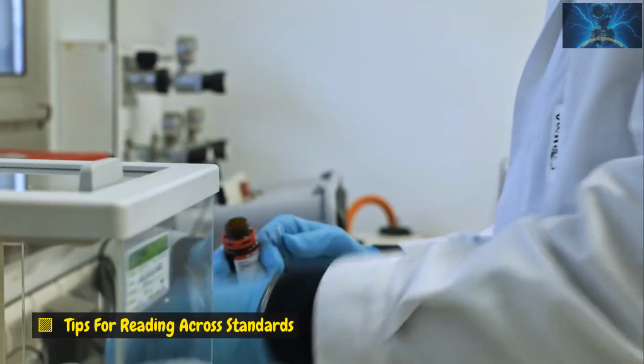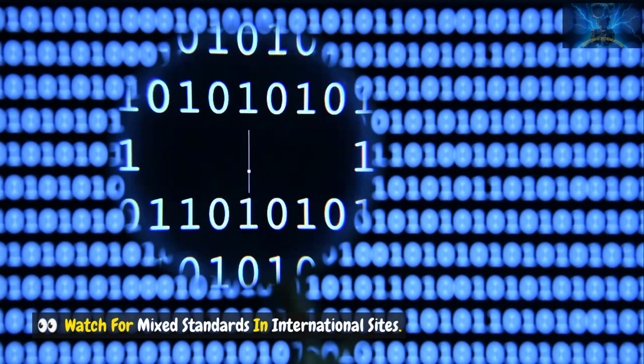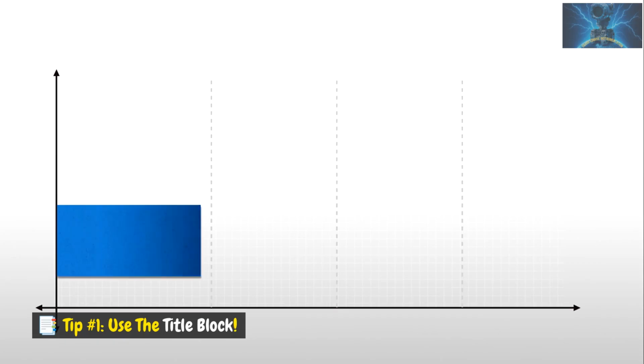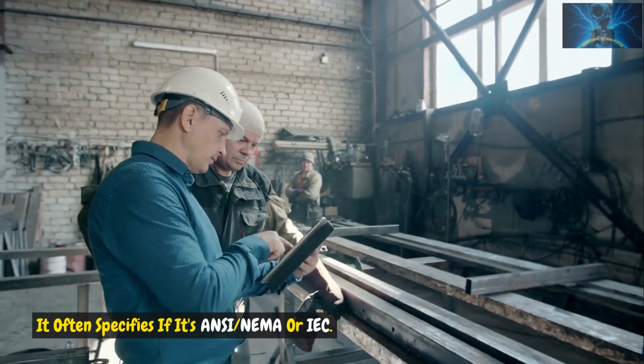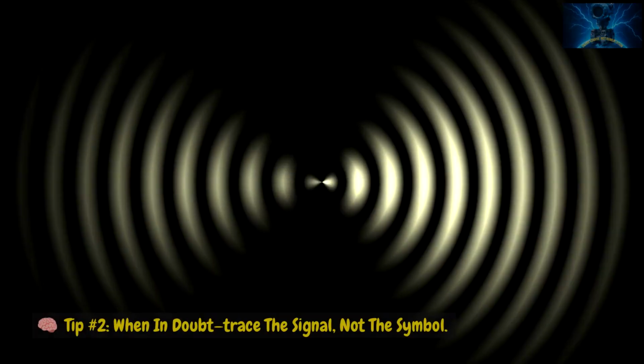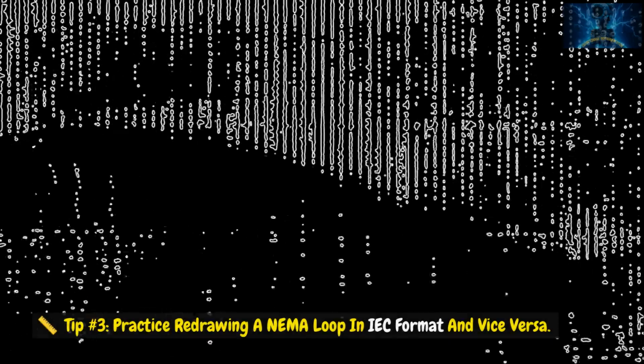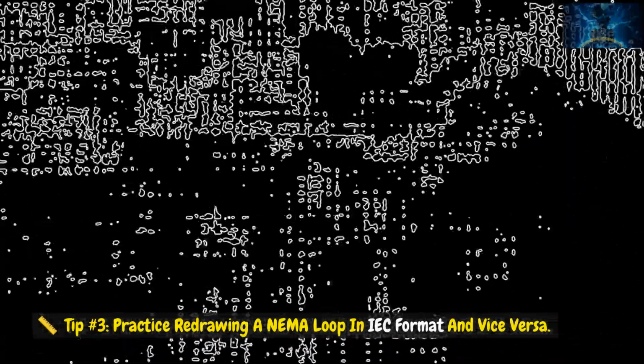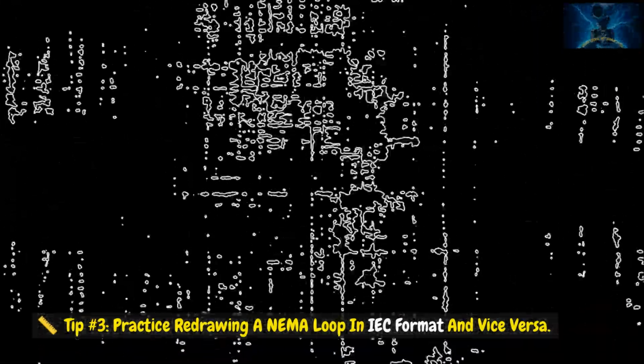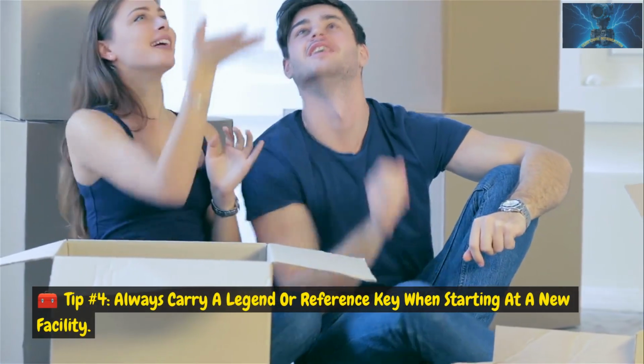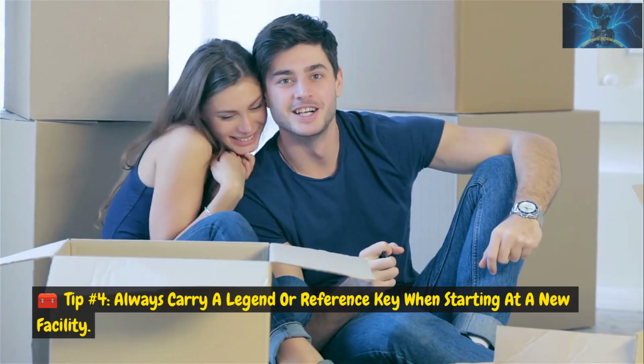Tips for reading across standards. Watch for mixed standards in international sites. Tip number 1: use the title block. It often specifies if it's ANSI, NEMA, or IEC. Tip number 2: when in doubt, trace the signal, not the symbol. Voltage and current don't lie. Tip number 3: practice redrawing a NEMA loop in IEC format and vice versa. It's a great learning tool. Tip number 4: always carry a legend or reference key when starting at a new facility.